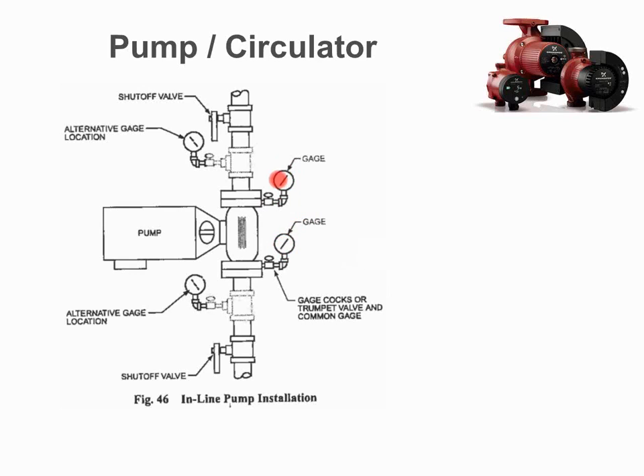So if you took the gauge and moved it from one tapping to the other and measured both of them, if the calibration of the gauge is off, it's going to be off on both of them, so now you will get a true reading of the pressure drop going across that circulator. Because really all the circulator is doing is taking water from one side, creating a pressure differential, and moving it across the system. So using the same gauge is your best application, and just make sure you have the tappings with the valves so you can do it.